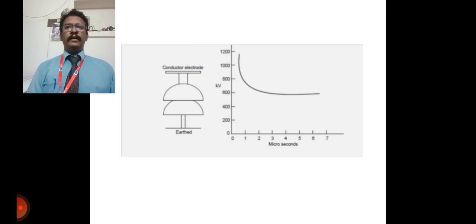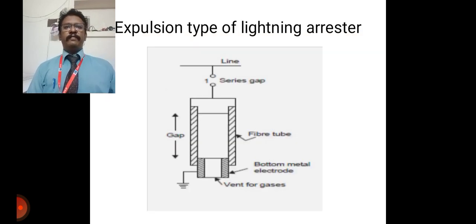This means that every operation at the rod gap results in the LG fault, that line to ground fault, and the breaker must operate to de-energize the circuit to clear the flashovers. The rod gap, therefore, is generally used as a backup for the protections. Next, we are going to see about the expulsion type of lightning arresters.